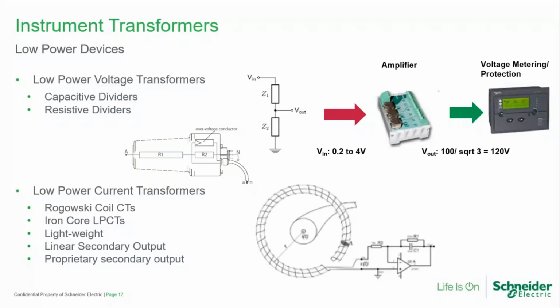we're able to remove requirements around primary fusing inside of switchgear. When you look at metal clad switchgear, the most common failure point inside of metal clad switchgear is either VTs or CPTs, and usually due to winding failure, usually due to environmental contamination over time. When you look at capacitive dividers or resistive dividers as alternatives for low power voltage transformers, you don't have the same types of failure points that you do with traditional inductive style wound transformers with CPTs and VTs as they are today. So you're able to remove a lot of those common failure points and get a longer lasting, more reliable style of instrument transformer.